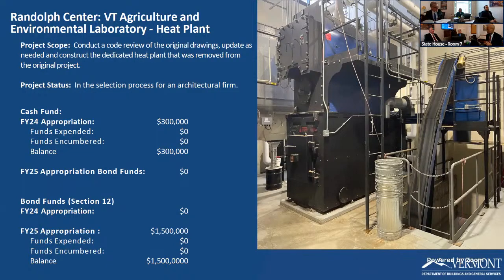They have been working with us and it's been okay, but lately we're having two issues. One, we're seeing a fluctuation in steam pressure. Yes, we can hit the high of 48, but then we'll drop down to 20. For the building, that's okay. The autoclave, it does not. That up and down pressure also isn't great for it.